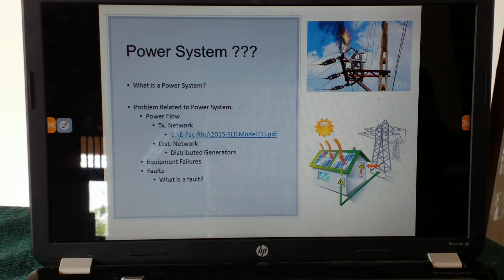So even in the distribution network, the flow direction depends on the availability of energy source. In the transmission network we know what the power flow will be, but in the distribution network, because of the nature of the distributed generators - almost all renewable energy - the availability of the energy source is almost non-predictable. They generate whenever energy is available, so we cannot predefine what the power flow will be. It is a very problematic system in the distribution network. Right now I can't know what the power flow is in my network in that regard.